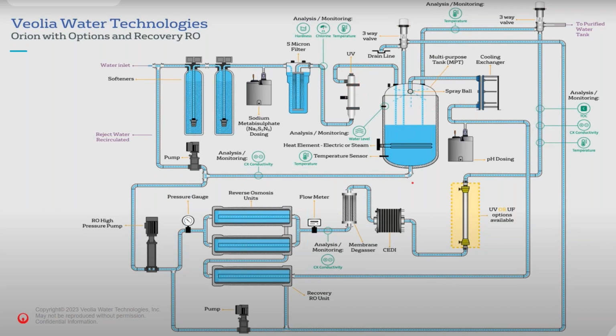The water then goes into a break tank. We tend to call this a multi-purpose tank. It is actually a break tank open to atmosphere. It's not a pressurized vessel, although it does have some hygienic features. It's made of stainless steel, it has dished ends, it has a spray ball, etc. The unit also houses a heating element, be it steam or electric, for hot water sanitization. I'll come back to that a little bit later. So from the bottom of the tank, the water flows out. We have a conductivity cell at this point here. We are essentially measuring the raw water conductivity.